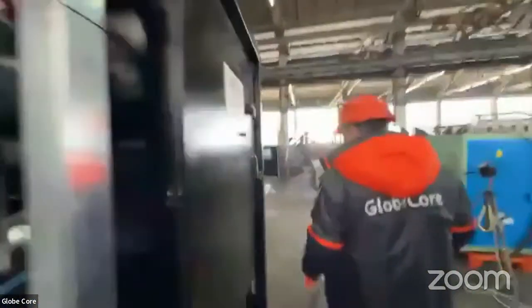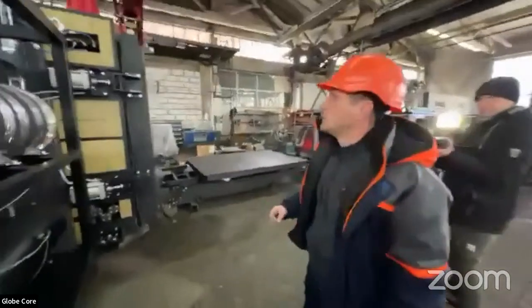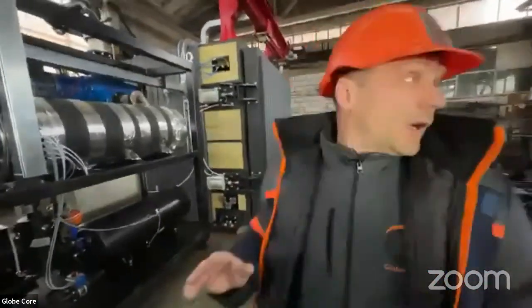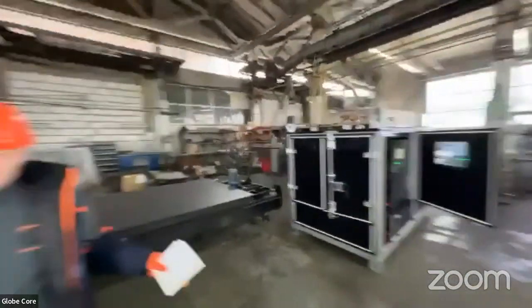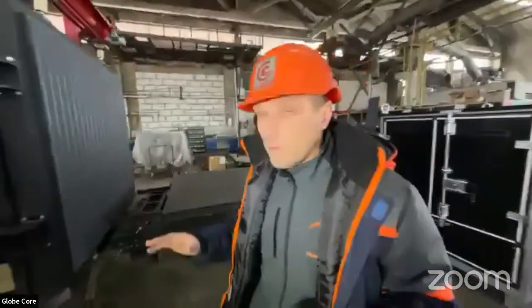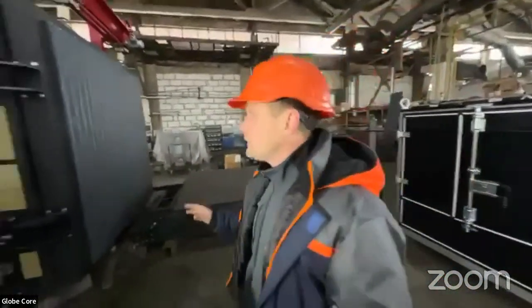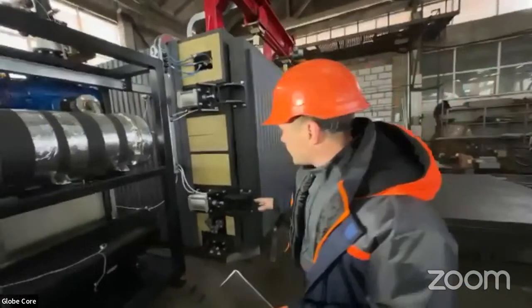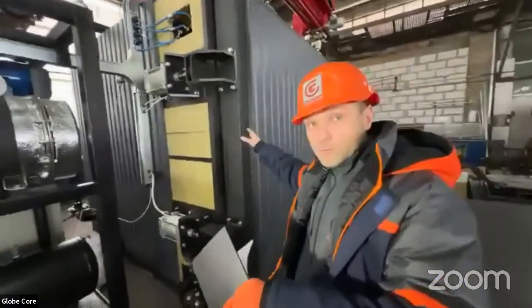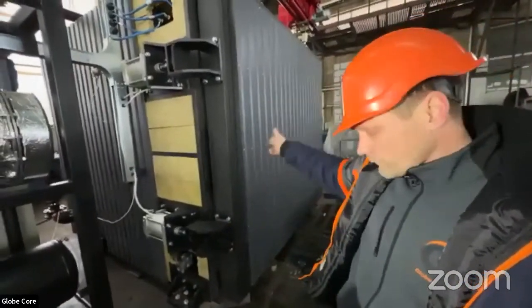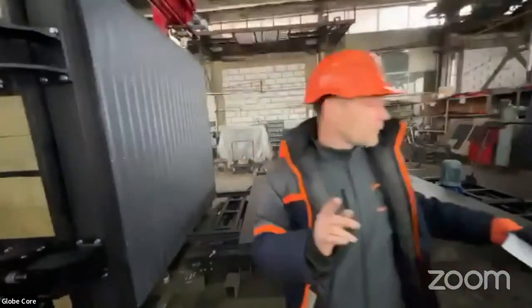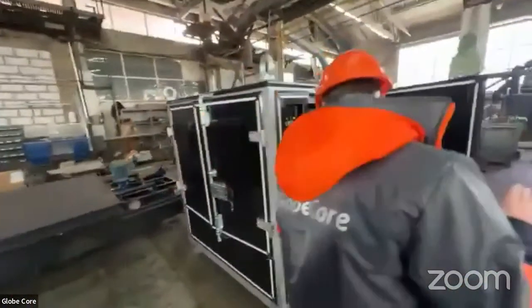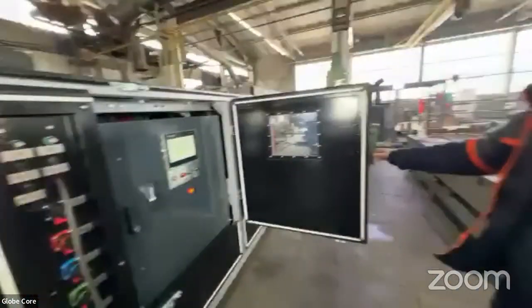Okay, briefly, this is about the vacuum oven. We have 2 machines in here, and this is to demonstrate the principal possibility of their combined operation. If the heating in the separate system, like vacuum oven, is supposed to be placed inside the oven, we can arrange the heating directly of the windings of the transformer using the low frequency heater. So let's go here. Start from this. So it looks like this.